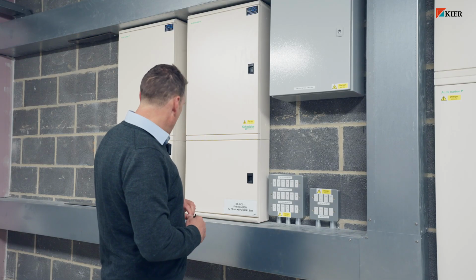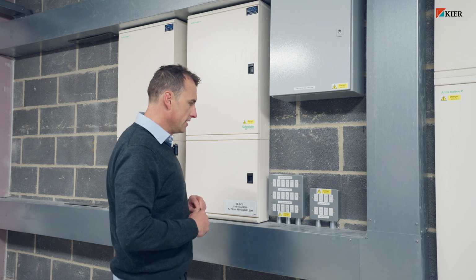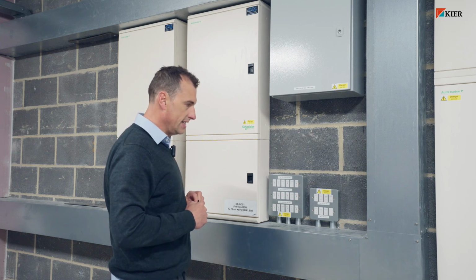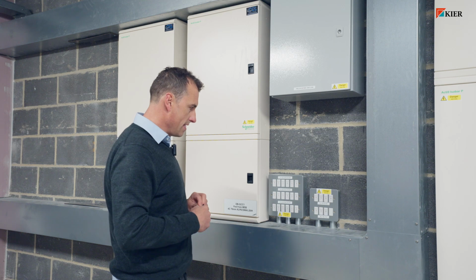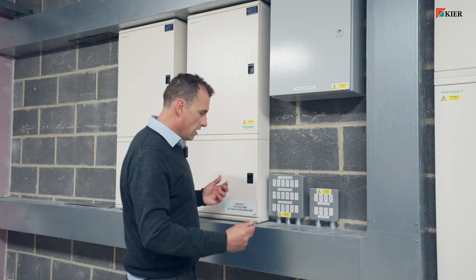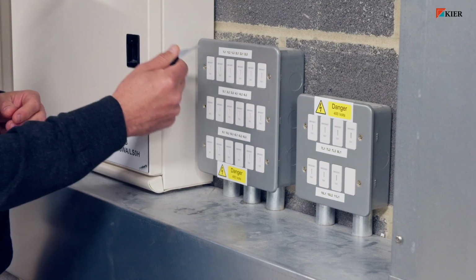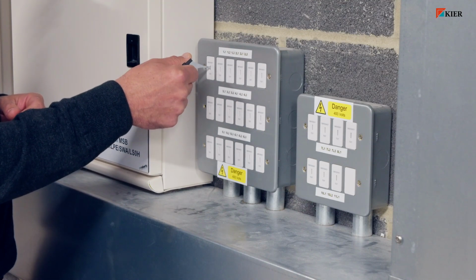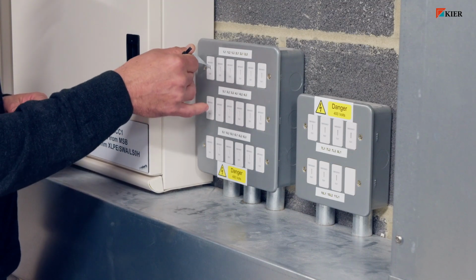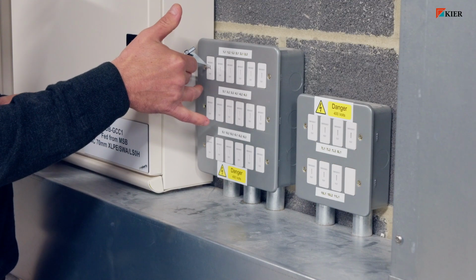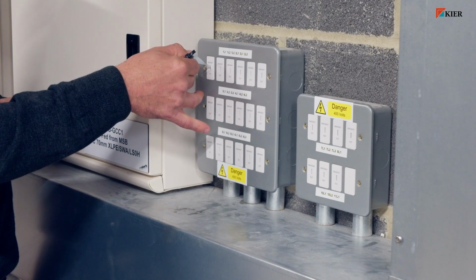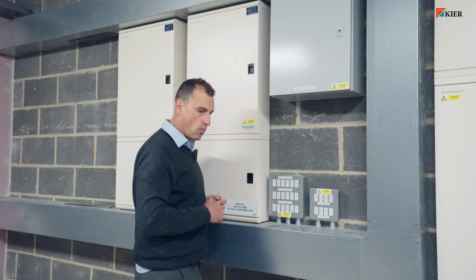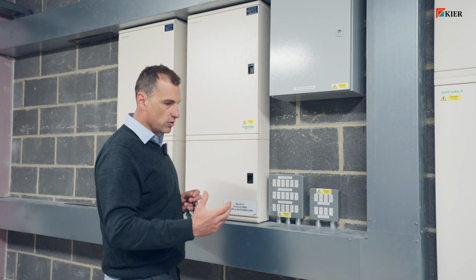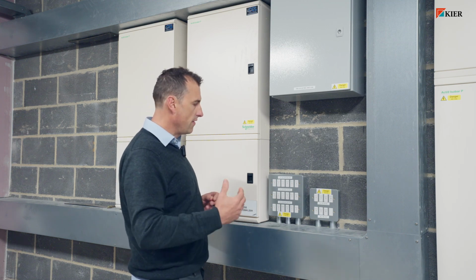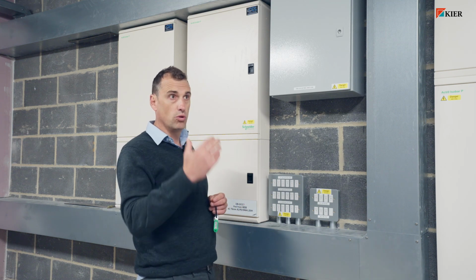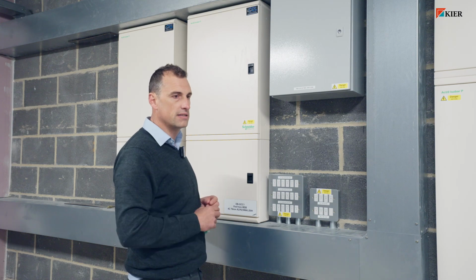At every lighting distribution board, there is a set of emergency lighting test key switches. In order to operate them for your maintenance, you just take your fish key, insert it into the electrical test switch, and just switch until you hear it click. And that will bring on the emergency light for a test. I just do need to also make you aware that when testing them, some lights will stay on. Those are the normal light fittings. However, you will see all the emergency lights will dim down slightly under test.